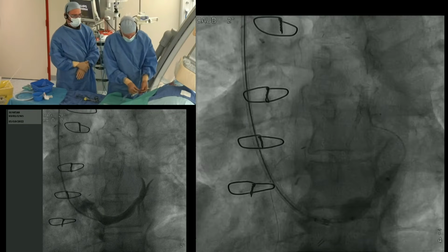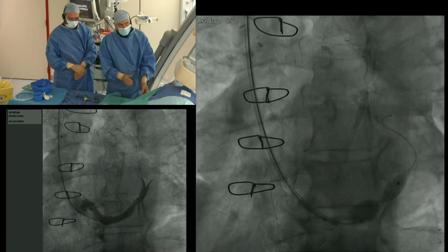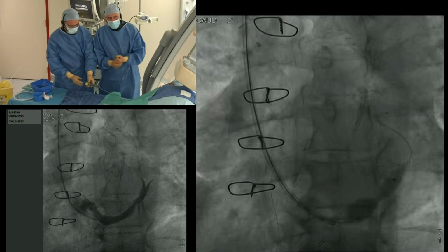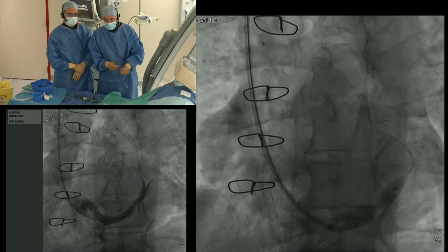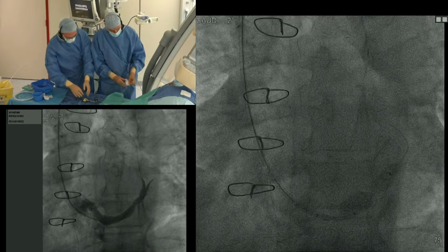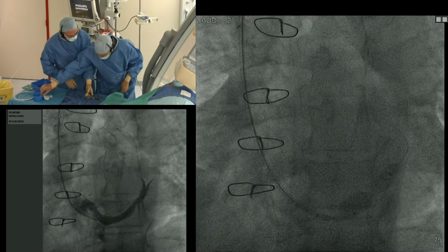I think it's good. It's a good example here, Pierre. And we have the feeling that the device is already a little bit bigger than the coronary sinus, which is a good way to lower the risk of embolization. Do you want to deflate the inflator, Thomas? Do you want to go by unscrewing it, or should I go negative first?